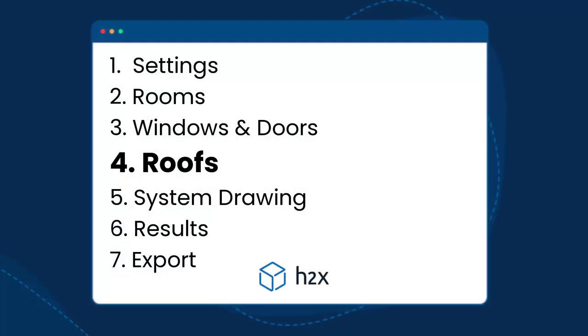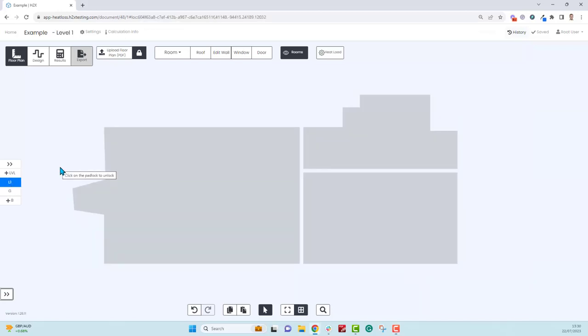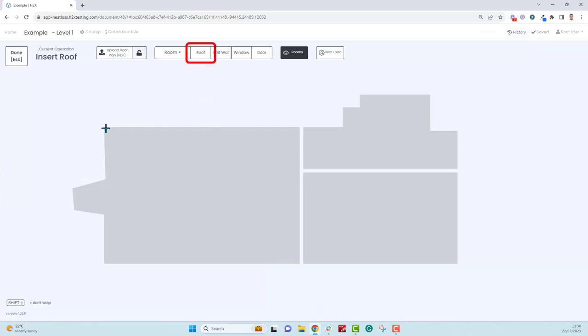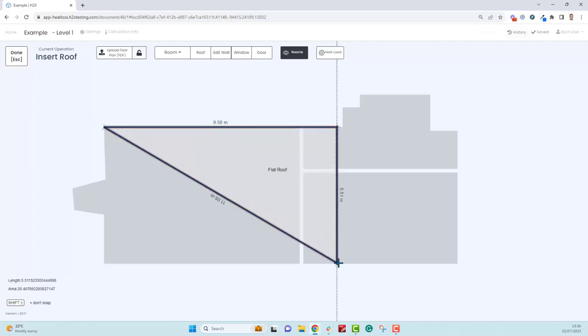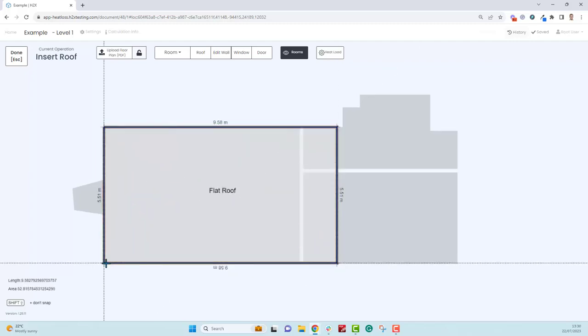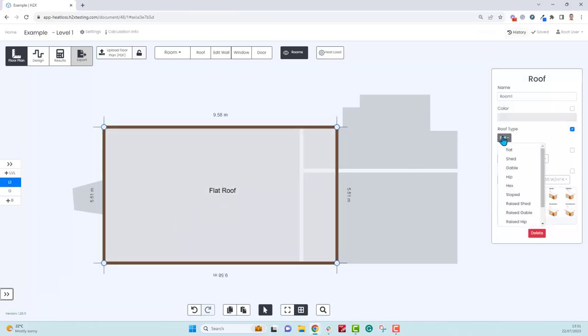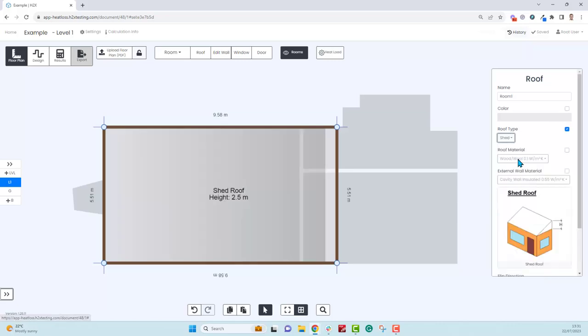The final step is to add a roof. You will have a flat roof by default, so if your building has a flat roof you don't need to make any changes. That will automatically be included in the heat loss calculations. If you wanted to add a different type of roof you'll need to create level above. Here you'll see in gray all the rooms from below. You can add multiple types of roof. Similar to how we drew different rooms below, you can add different types of roofs. If the roof goes over multiple different rooms, the heat loss will be proportionately distributed between them. If we go over part of these rooms just like this, it will default to a flat roof, but then in the properties here there's a range of layouts to choose from and you can edit the dimension properties for each one.